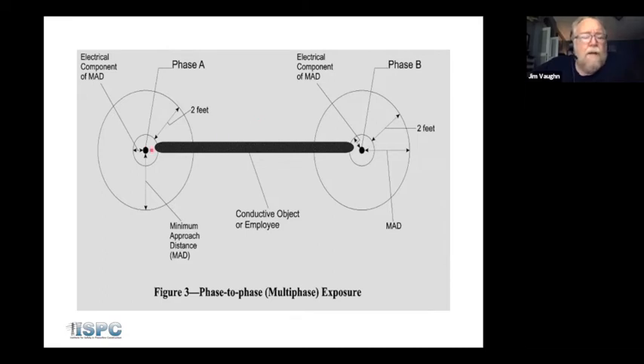But if in distribution you have effectively covered up these conductors, then your exposure is only this phase, so your exposure is phase to ground. And that's what shortens up your MAD distances. This is the way that OSHA and consensus standards agree to determine what multi-phase exposure is. So if you're covering B and C phase, working on A, then you only have a phase-to-ground exposure.